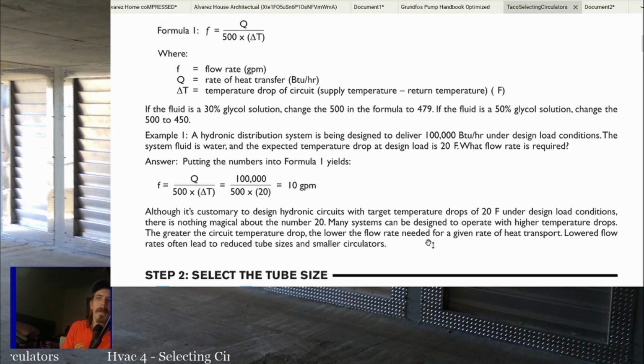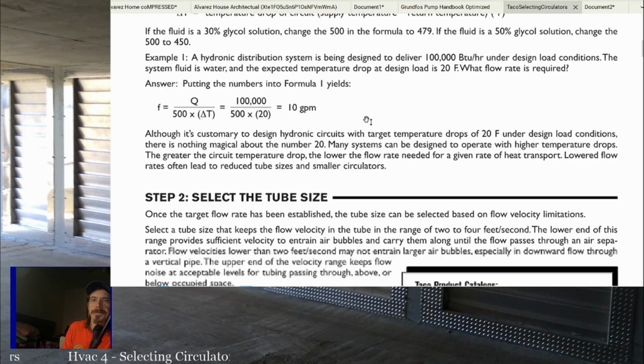you can just get away with that. But in those cases where you can't, where the pump you put in can't handle the head pressure drop throughout the system, or can't handle the flow rate that you wanted, especially on cold days, the system's not going to perform well anymore. So just putting in the wrong circulator there completely made it so not everything operates well anymore. And that's why being able to size a circulator is so important with a boiler system.